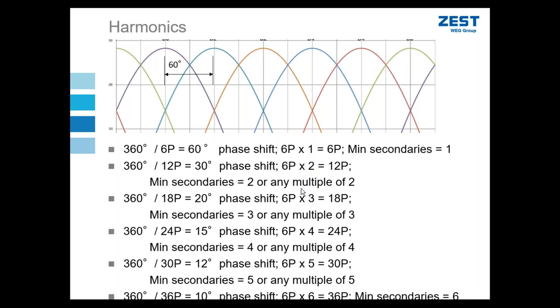My rectifier will have 4 6 pulse bridge rectifiers. My transformer can have 4 secondaries. I just have 2 secondaries that are the same phase angle as the other 2 secondaries. So that's why we talk about the minimum number of secondaries, but I can increase that to any multiple of 2 and still have a 12 pulse system. If we look at 18 pulse, 360 degrees divided by 18 means I need a 20 degree angle between my peaks, which means my phase shift needs to be 20 degrees. I need at least 3 bridge rectifiers to give me my 18 pulse solution. And likewise, I need at least 3 secondary windings in my transformer, or any multiple of 3.